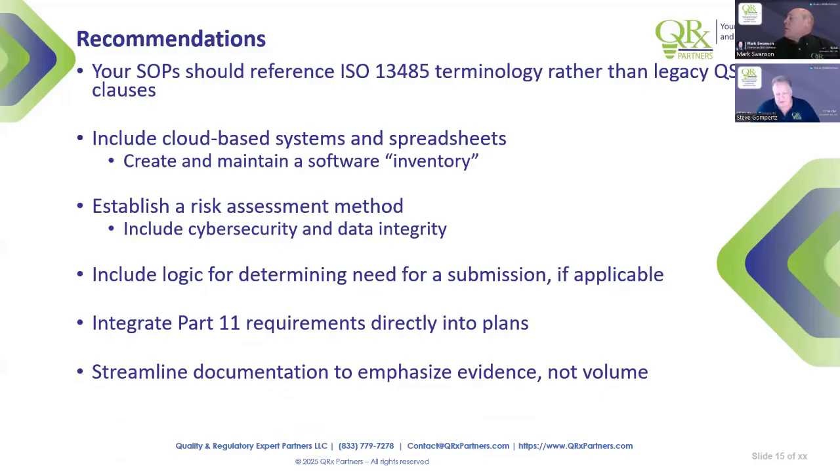And again, determine the required documentation based on the risk assessment, right? The risk assessment is going to tell you what activities to perform. Those activities are going to dictate what documentation is required. So it isn't just, oh yeah, we got to generate lots and lots of documentation and records in order to show validation. You may not have to, and that's why you definitely want to leverage this guidance document.